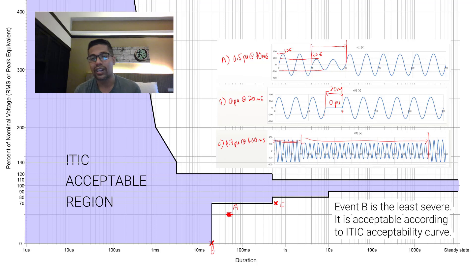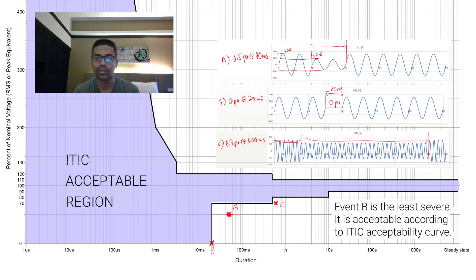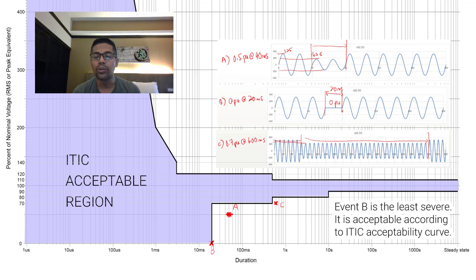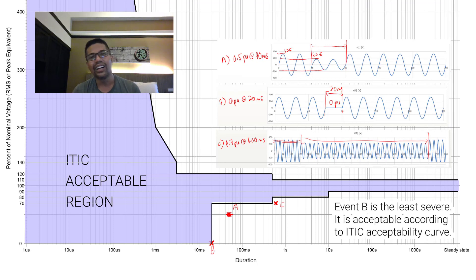As an exercise, get some waveforms, convert them into magnitude and duration, and plot them on the acceptability curve. Then you can determine which events are acceptable and which are not. In these three events, only Event B is acceptable; Events A and C are not.